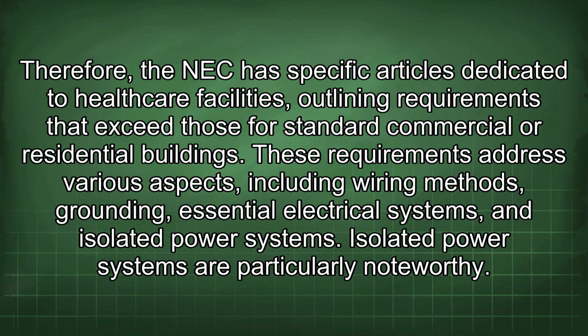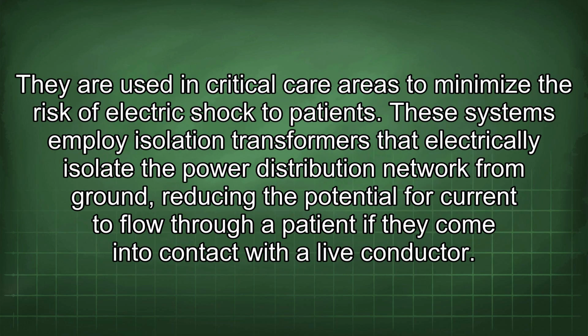Isolated power systems are particularly noteworthy. They are used in critical care areas to minimize the risk of electric shock to patients. These systems employ isolation transformers that electrically isolate the power distribution network from ground, reducing the potential for current to flow through a patient if they come into contact with a live conductor.